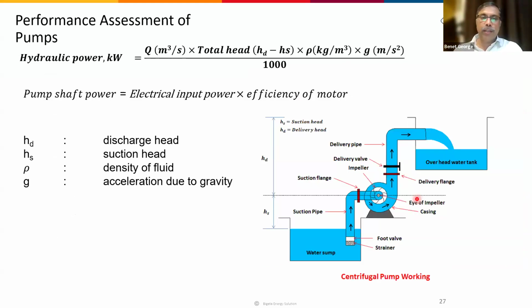So this is the formula for evaluating the performance of the pump. You can see here the pump is sucking water from the sump, and there is a foot valve, a strainer, then a suction pipe, an impeller, a pipe and a valve, and it is going to an overhead tank. So we have to understand what the total head is. Suction head is the distance between the impeller eye and the top of the water level, and discharge head is from the impeller to the top of the pipe. So the total head we have to evaluate.